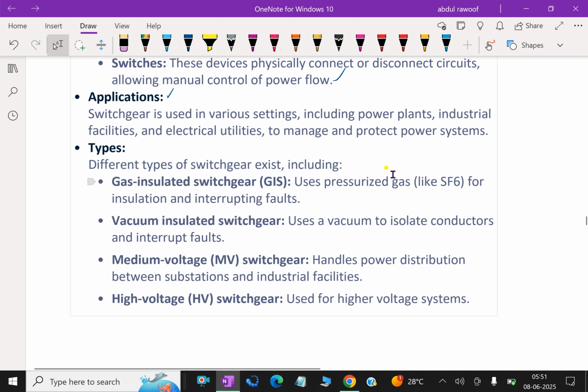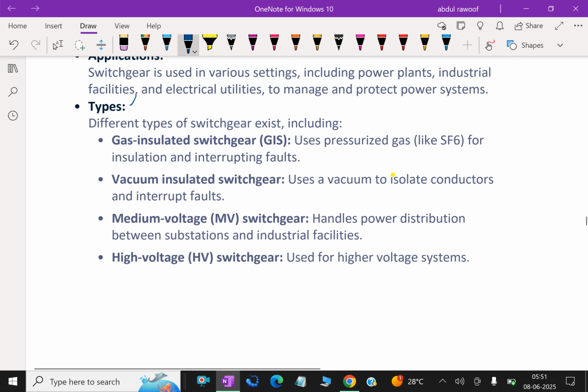Types: different types of switchgear exist, including gas insulated switchgear, which uses pressurized gas like SF6 for insulation and interrupting faults, and vacuum insulated switchgear, which uses a vacuum to isolate conductors and interrupt faults.